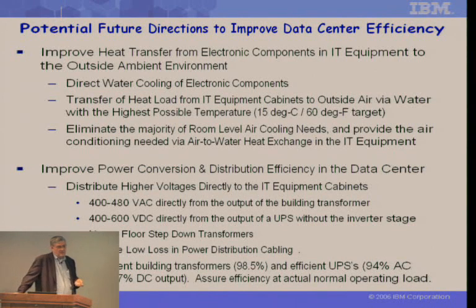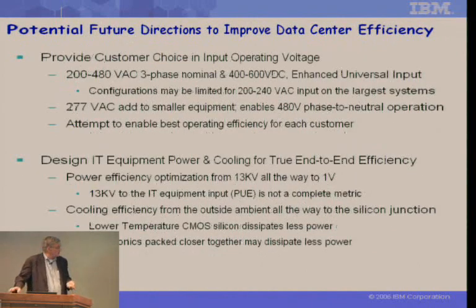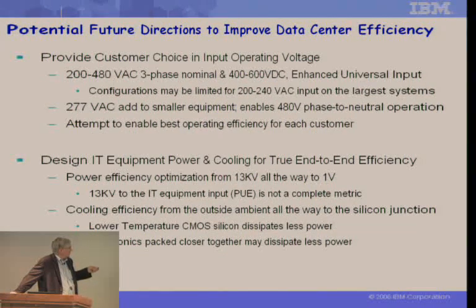Distribute high voltage in the data center. This is really important. High voltage is all over, so let's just use it directly to our servers. Either ship around 400 to 480 volts directly from the output of the building transformer, or you can take 400 to 600 directly from the output of the UPS without having that inverter stage. No on-floor step-down transformers, low loss cabling, efficient building transformers. We can get very high, near 99%. UPSs, I think a number earlier was mentioned, 92 to 95. And if you take the DC output and eliminate that last inverter stage, you can get up to 97%. So into our system then, we could potentially take AC, anywhere from 200 to 480 AC, or we could take 400 to 600 DC.